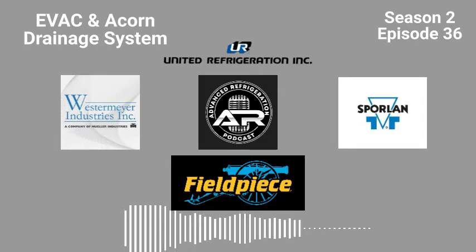On another note, the way these are piped is very specific. The way the fittings are, they don't want you using 90s. They want you using 45s because they don't want a sharp turn on these, because of the velocity going through there. If it's a 90, it could actually shatter the pipe and go right through. So in our training facility in Fullerton, we put in pieces of clear plexiglass tubing throughout, so you can see how fast this thing just takes off. See a turd going through there at Mach speed? You know what? Now I've got a thought for next time I'm in Fullerton.